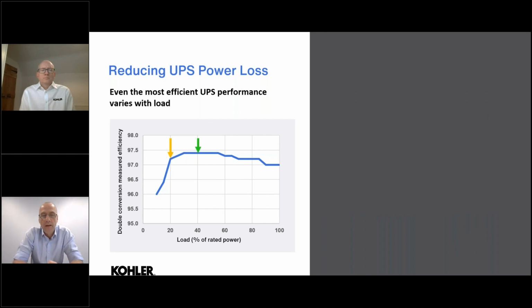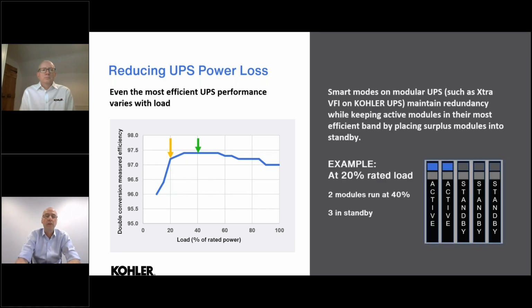But these units, all units, will have operating bands for efficiency, and many UPSs are tuned for the best efficiency towards a mid power range on the basis that you are going to have redundancy in the system. But with any systems, the efficiency will drop off at low loads, and we can see here the most efficient band for this is about 40–50%, and it drops off significantly from 20% down. So what we want to do is keep those units running at their most efficient, and this is where the smart modes on UPS comes in, such as the Xtra VFI on the KOHLER UPS. We want to maintain redundancy, but also only have the units required to run as required.